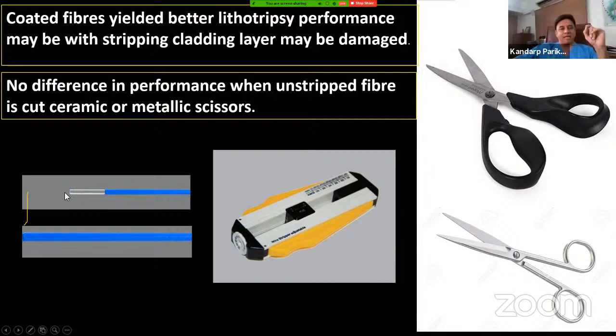And secondly, there is a laser light which is coming out through it. I always keep it at a very low setting. The pilot is set at 1. So there is a minimum laser light seen falling on the stone. So it will not distract my vision. And it has been studied by Dr. Drexler, and they have suggested that the coated fiber yielded better lithotripsy performance, maybe because with stripping the cladding layer may be damaged. That's why you don't need to strip the fiber. Once you use the laser fiber for 15 to 20 minutes, Dr. Drexler always suggests to cut the tip of the laser fiber with this ceramic or a metallic scissor during the surgery, for up to 5 mm, 6 mm, the fiber should be cut.